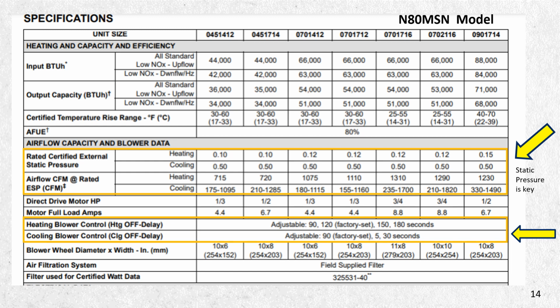Then you want to look at this, one of the specification sheets that most people don't even bother to look at, but it's very important, especially right here. Rated certified external static pressure. Make sure whatever model number you have that your static pressure in heat is rated for that, and your cooling static pressure is this, and then here it will create your airflow here. So always keep that in mind, and we'll go through that here in just a minute. And you'll also look at the drive, the horsepower. You have a 1/3 horsepower on the 45, and you also have a 1/2 horsepower, and you go back to a 1/3 on the 070s.